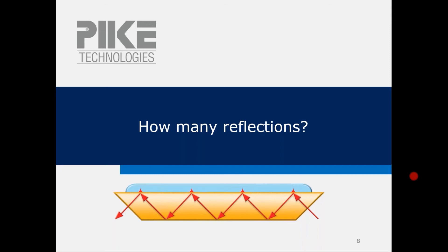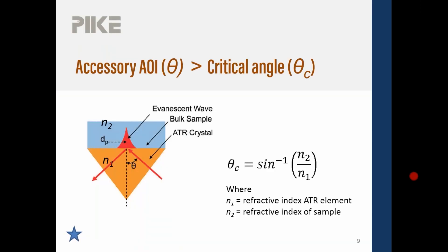We put that as the number of reflections on the sample. So to make ATR work, we must have the angle of incidence of the accessory greater than the critical angle. So in this little cartoon, this angle right here must be greater than this calculation right here. And the critical angle θc is a function of the refractive index of your sample n2 and the refractive index of the crystal n1. So let's go and do a quick Pike Calc.